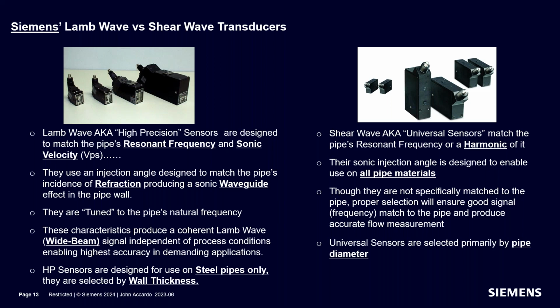As I said earlier, the first 3 generations of flow meters, all we used was Lamb wave. And so there were many different types of transducers depending upon what your pipe was made out of. When we ventured into the high-end applications with the 990, we decided to continue to use the Lamb wave, but rather than make them for copper pipes and ductile iron pipes and copper nickel pipes and so forth, we just brought back the ones for steel pipe, because most of the applications that require high degrees of accuracy are in steel pipe. Applications such as gas pipelines, hydrocarbon pipelines, those are all in steel pipes.